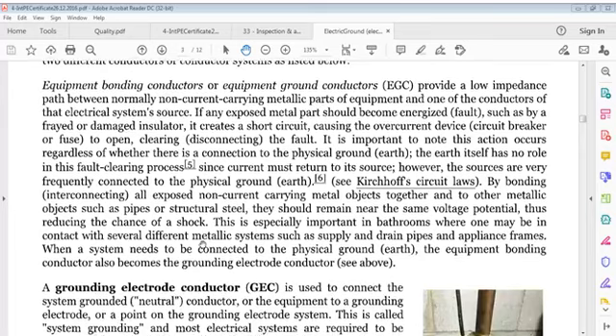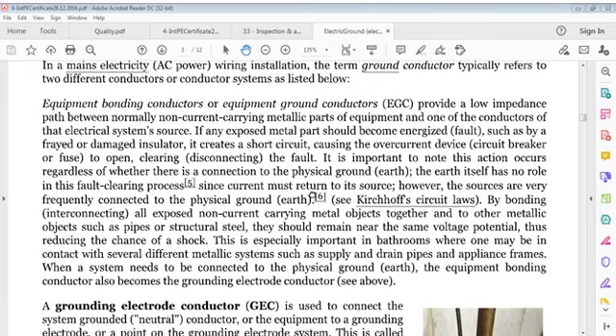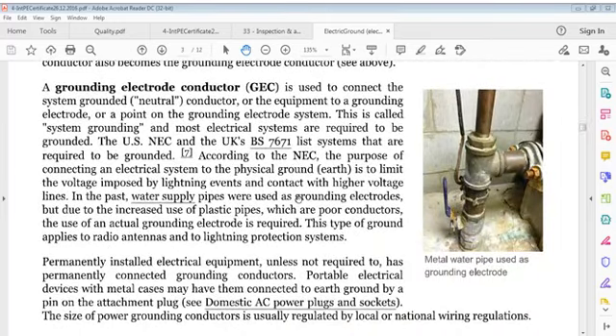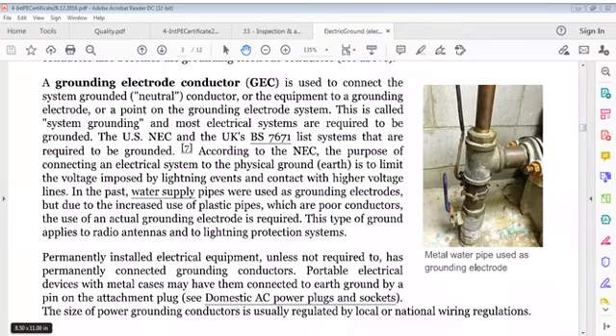A grounding electrode conductor, what is that? This was the equipment bonding conductor, equipment ground conductor. Now it is the grounding electrode conductor. This is a photo of a metal water pipe used as a grounding electrode. The grounding electrode conductor, GEC, is used to connect the system grounded conductor, that is the neutral conductor, or equipment to a grounding electrode or a point on the grounding electrode system.